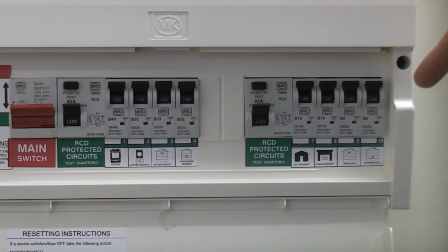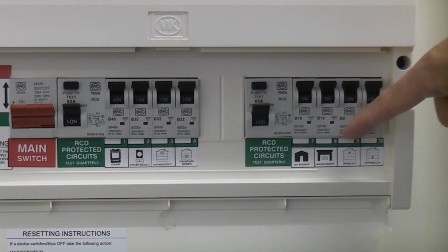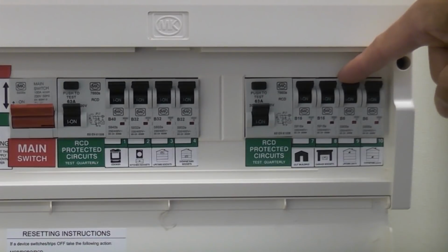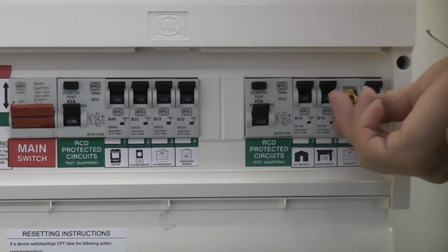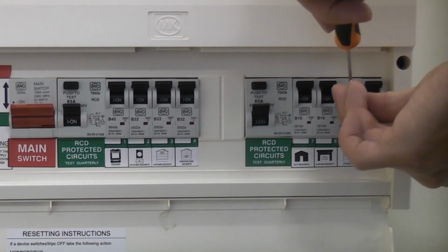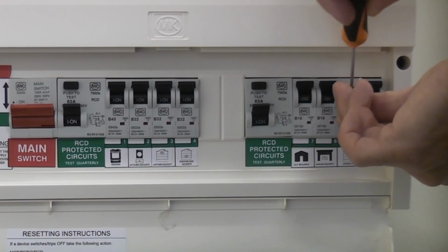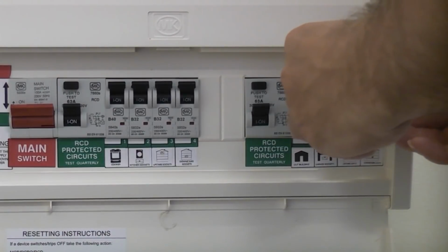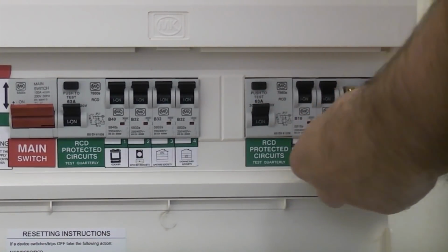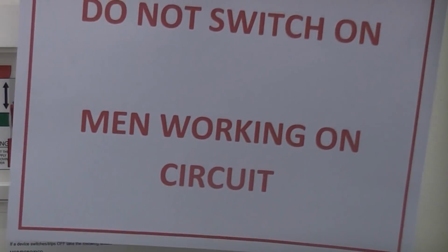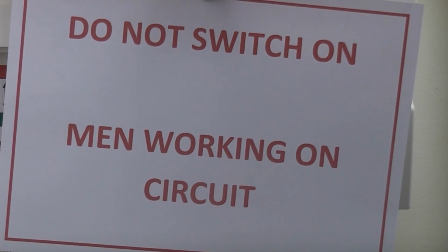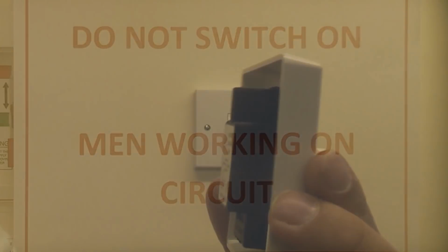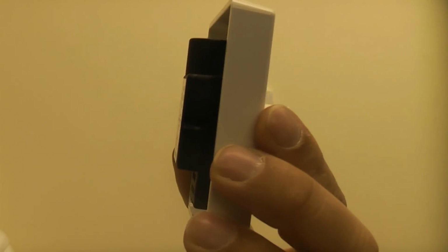I'm now at the consumer unit. I'm going to switch off the correct circuit breaker, which is for the upstairs lights. I'm now going to lock that off using a lock-off device. This will prevent anybody from switching it back on. I'm then going to lock that off using a padlock. And then finally I'm just going to put a notice on the front there telling people not to switch it back on.